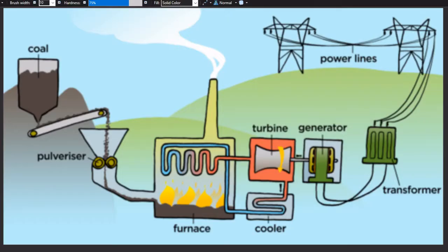For the majority of power production methods, including coal plants, this is done by heating water and using the resultant steam to spin these turbines. In coal plants, it typically goes like this. The coal is pumped into the plant, going through a preliminary pulverization before being dumped into the furnace. This is also referred to as the boiler, as the coal here being burned causes water that is being pumped through pipes that run through this furnace room to boil.